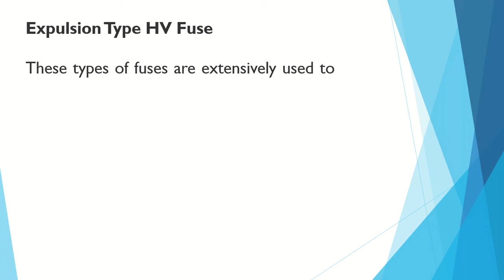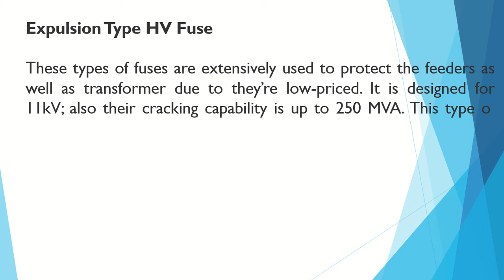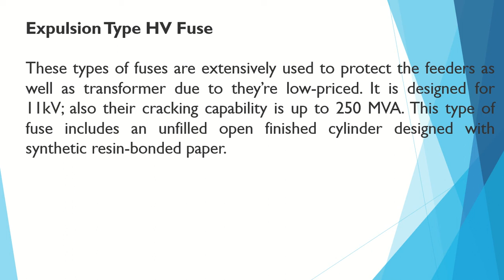Next, the expulsion type HV fuse. These types of fuses are extensively used to protect feeders as well as transformers due to their low price. It is designed for 11 kV, and their breaking capacity is up to 250 MVA. This type of fuse includes an unfilled, open-ended cylinder designed with synthetic resin bonded paper.